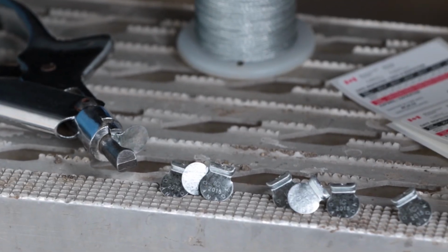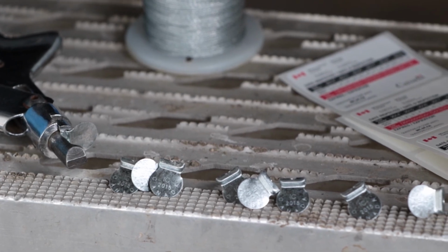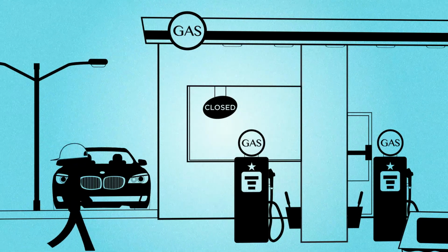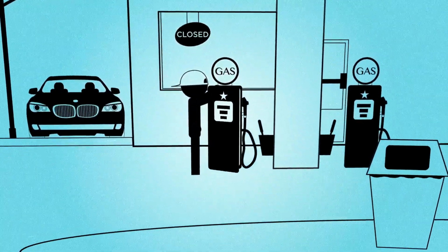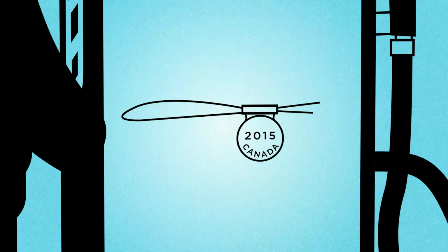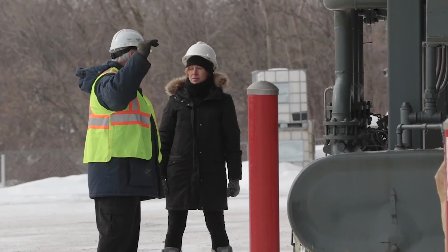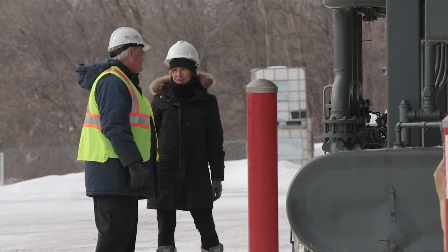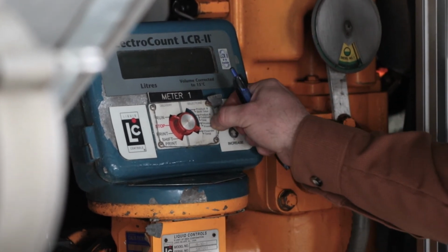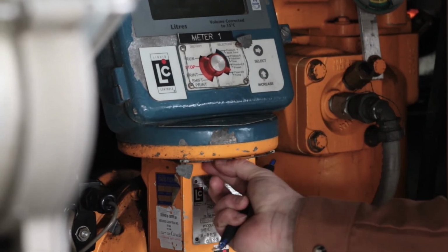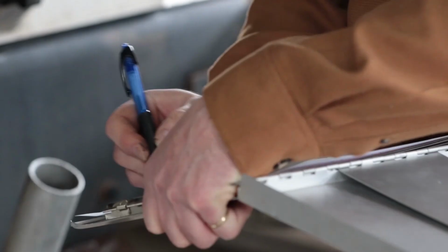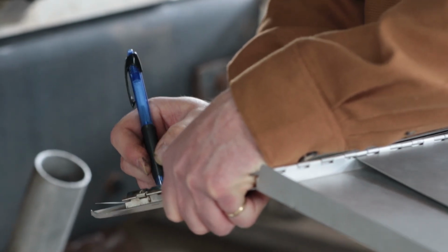Seals act as deterrents to those who might be tempted to alter a device with the intention of using the device fraudulently. They also deter improper repairs or maintenance and identify the organization that has performed the last inspection or repair. Upon certification of a device, or in such cases where enforcement action by Measurement Canada inspectors is warranted, sealing procedures and annotation of the audit trail parameters, both as found and immediately prior to sealing, are an imperative part of the inspection and reporting procedures.